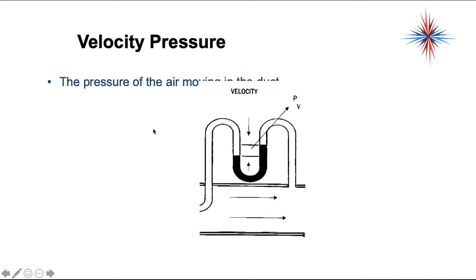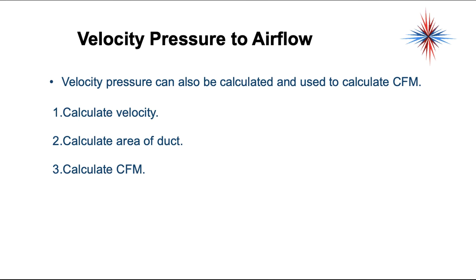Velocity pressure is the pressure of the air moving in the ductwork. It's not the outward pressure — it's the pressure of the air stream itself. Velocity pressure can be calculated and used to calculate CFM, which is the amount of air being moved. We calculate the velocity, calculate the area of the duct, and we can calculate the CFM.